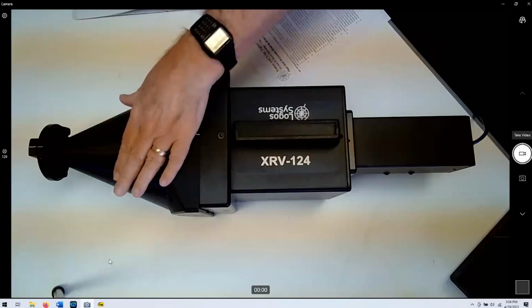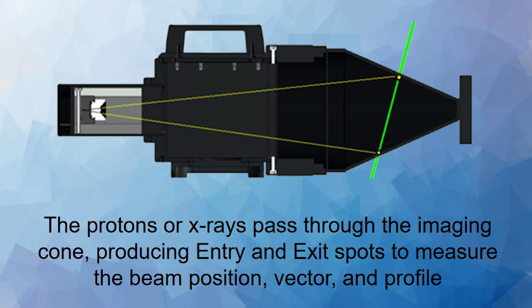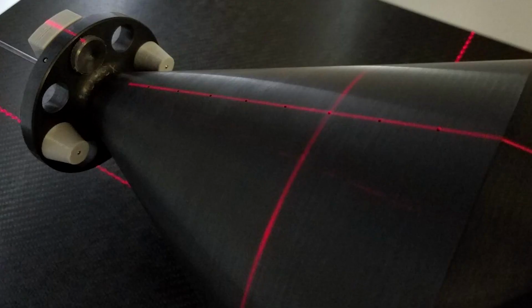As features from the diagram are discussed, their locations on the live video camera will be pointed out at the same time. The main purpose of the XRV-124 imaging cone is to convert the invisible proton or X-ray radiation beam into spots of visible light that can be captured by the digital camera at the opposite end of the Phantom.